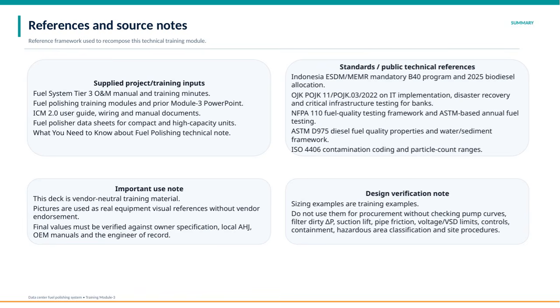These include Indonesia's mandatory B40 biodiesel program and biodiesel allocation targets for 2025, banking regulations on IT and disaster recovery, as well as internationally recognized frameworks like NFPA 110 for fuel quality testing, ASTM standards for diesel fuel quality, and ISO contamination coding. Together, these standards help ensure best practices and regulatory compliance. It's important to highlight that this training material is vendor neutral. Any pictures of equipment shown are for visual reference only and do not imply endorsement of any particular brand or vendor. Also, whenever you use or apply the information here, make sure to verify final values with the specific owner specifications, local authorities having jurisdiction, OEM manuals, and the engineer of record.